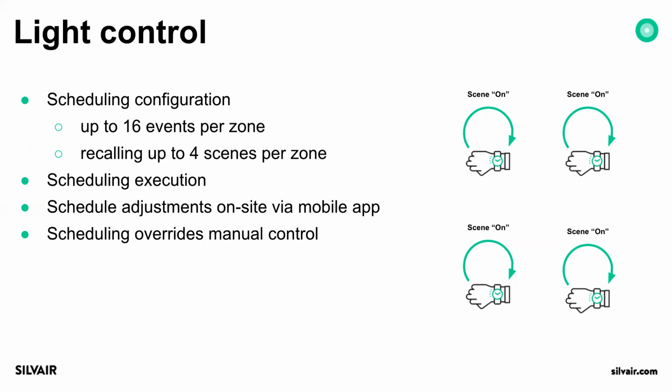I've mentioned before that the scheduling events and the profiles are configured into individual nodes. Each individual node running the scheduling has the appropriate configuration of scenes, the configuration of events, and of course each individual node tracks the time and synchronizes the time with the network.